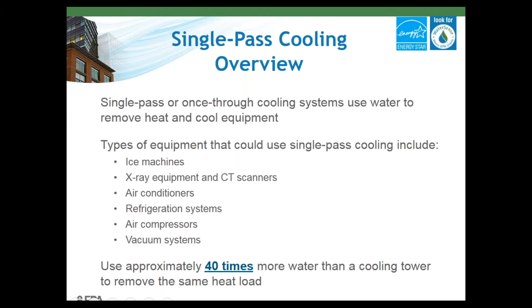Single pass cooling is commonly used to cool medical and laboratory equipment, vacuum pumps, air compressors, and refrigeration systems. And often the flow of this water is controlled with a solenoid valve, so the water flows when a motor or compressor is running. Unfortunately, with some really old models, where the valve fails, the water just flows continuously. And when this water is flowing continuously, you're just going to see a lot of water used. As we go to the next slide.